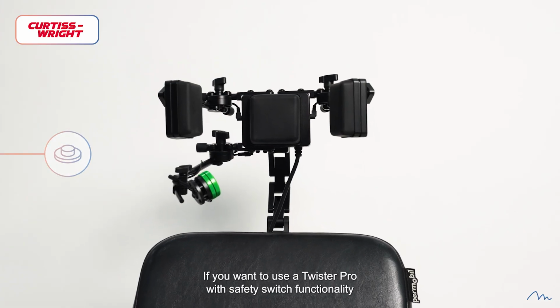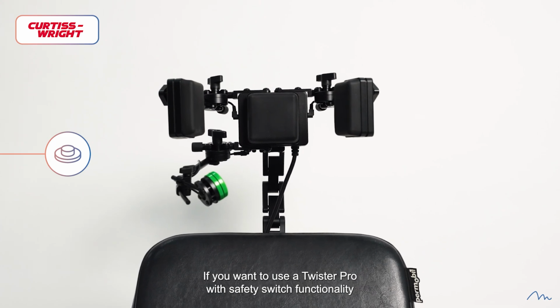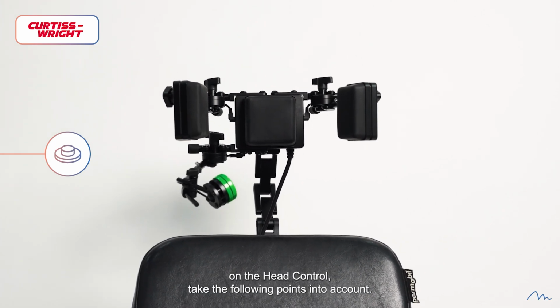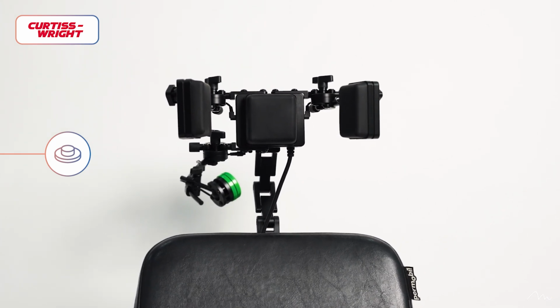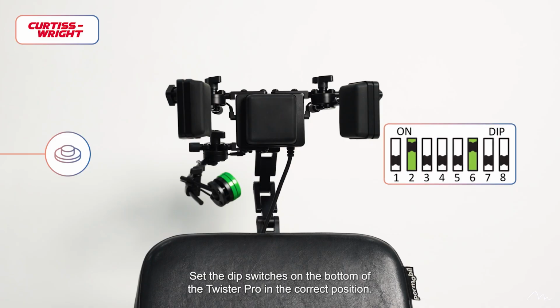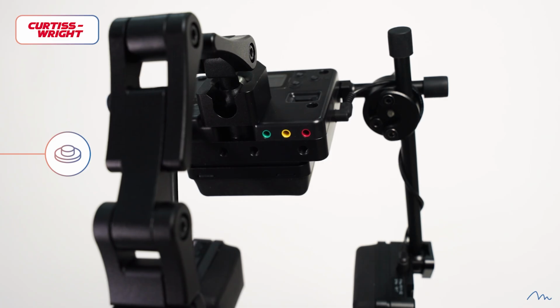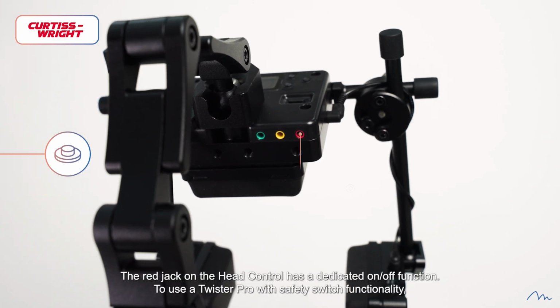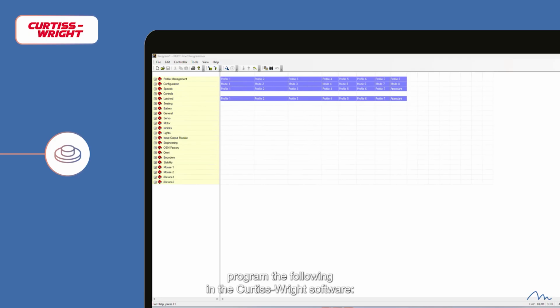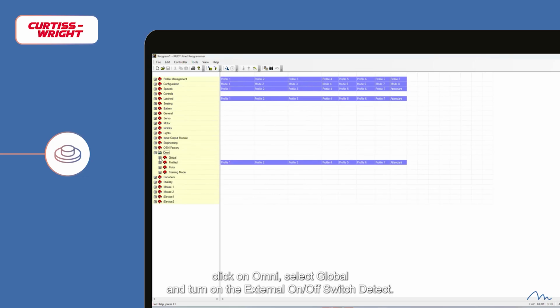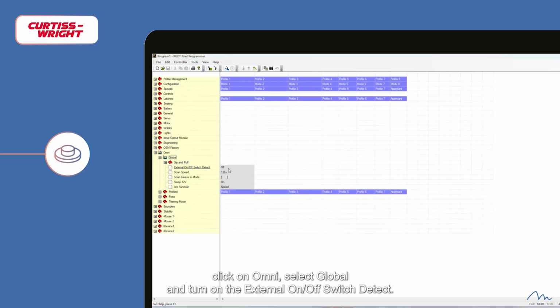If you want to use a Twister Pro with safety switch functionality on the head control, take the following points into account. Set the dip switches on the bottom of the Twister Pro in the correct position. The red jack on the head control has a dedicated on-off function. To use a Twister Pro with safety switch functionality, program the following in the Curtiss-Wright software. Click on Omni, select Global, and turn on the external on-off switch detect.